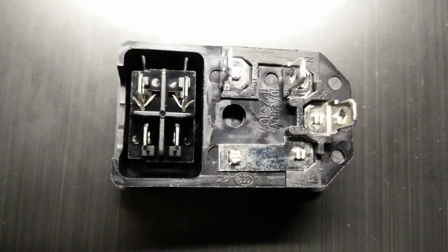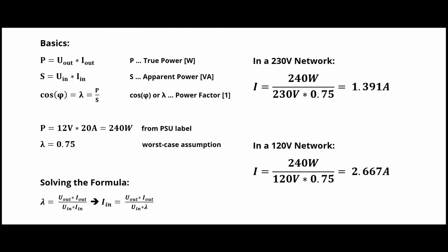The switch shipped with a 10 amps fuse, but with the following calculation I realized that with my country's 230 volt network, a 2 amps fuse should suffice as well. With a 120 volts infrastructure, I'd use a 3 amps fuse.